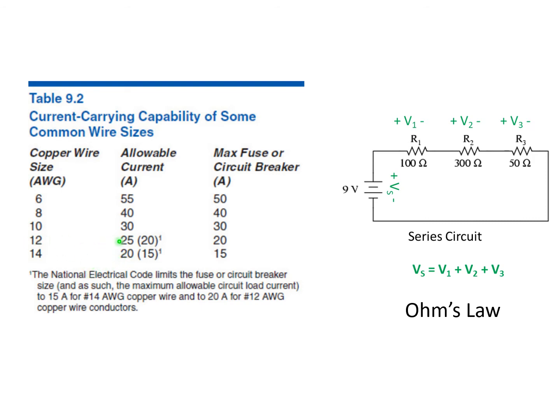12 gauge can carry 25 amps, but it's fused at 20. This is what a lot of your house wiring, 14 and 12, are what's used for most of your 110 volt house wiring, the outlets, ceiling lights, those kinds of things. And then you start getting into the heavier wire, the 10 gauge. Allowable current's 30 amps, and it can be fused at 30. 8 gauge is 40 amps, and 6 gauge is 50.